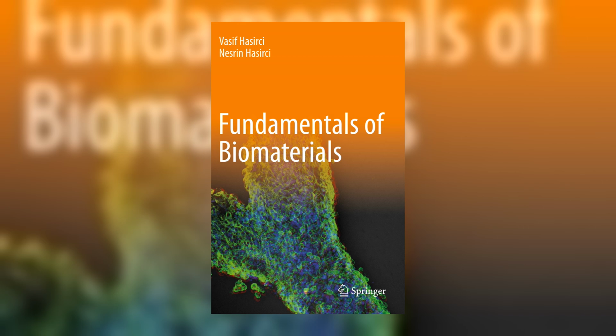This is the cheapest first tier gate of the ISO 10993 battery, the one test even the simplest catheter cannot skip. The generative move is this. Cytotoxicity is dose delivered to a proxy tissue. So every knob, extract ratio, time, cell line tunes the delivered dose.